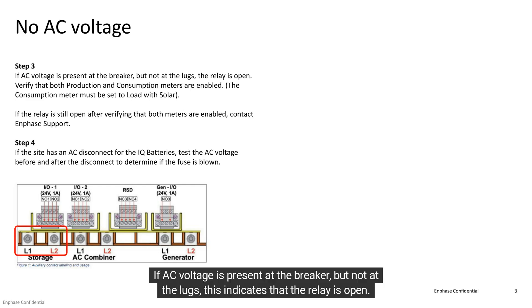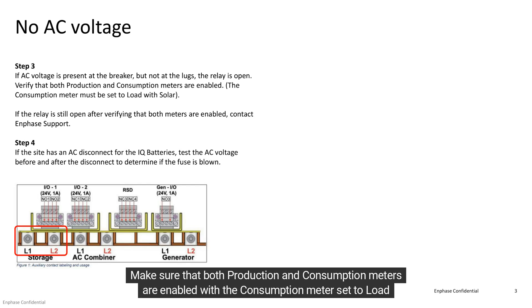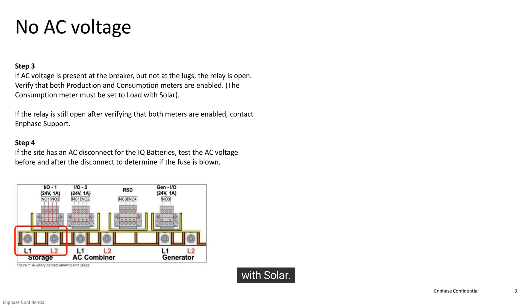If AC voltage is present at the breaker, but not at the lugs, this indicates that the relay is open. Make sure that both production and consumption meters are enabled with the consumption meter set to load with solar.